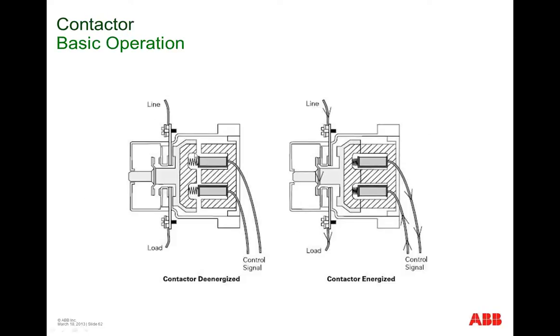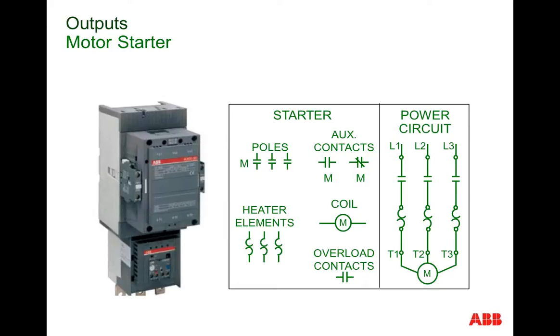Here we see a contactor de-energized. The electromagnet is not receiving electricity, hence we're not conducting power to the motor. We energize the contactor by putting 120 volts across the coil. We see that the switch is closed and we're conducting power to the electric motor. Now, a contactor plus what we call an overload relay, which is the bottom device here, combined together form what we call a motor starter.